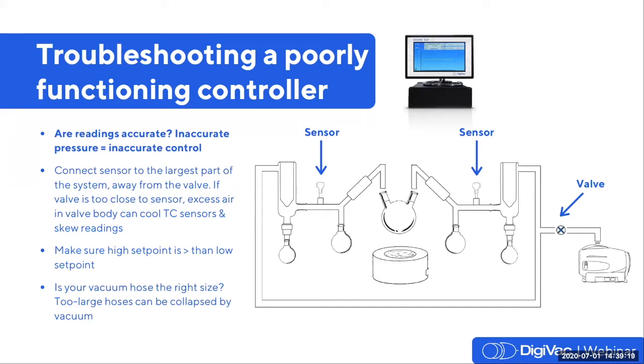Also, we'll want to make sure that our high set point is higher than the low set point, obviously, and also ensuring that our vacuum hose is the right size. Too large hoses or those with too thin of a diameter wall can be pulled closed by the force of the vacuum generated by the pump. And we can always assist you in choosing the right hose for your pump and your application.